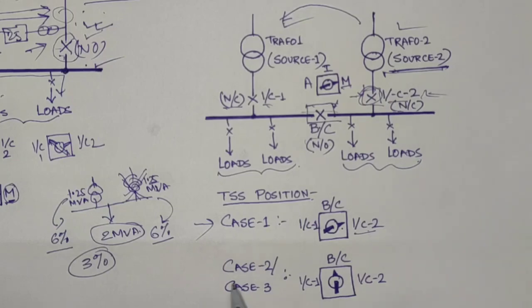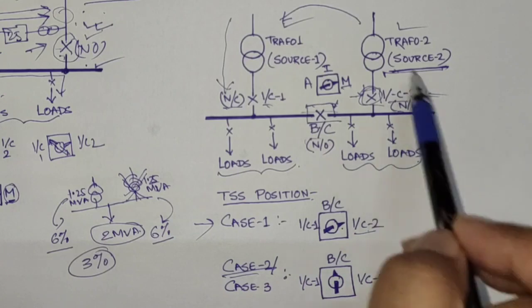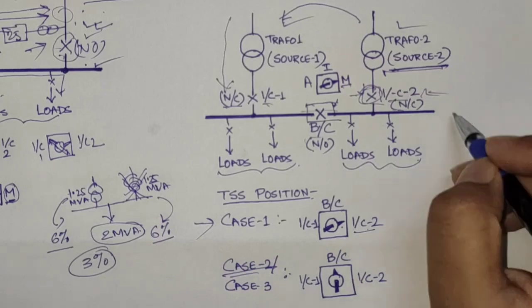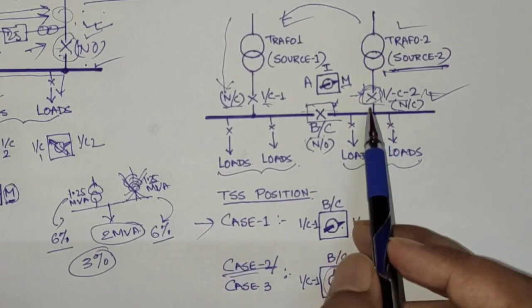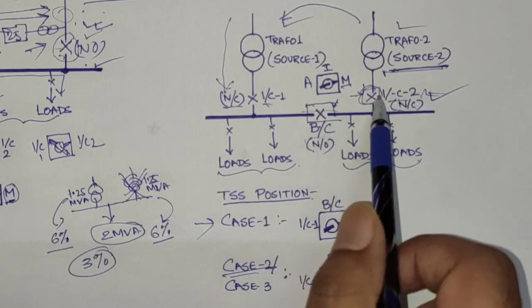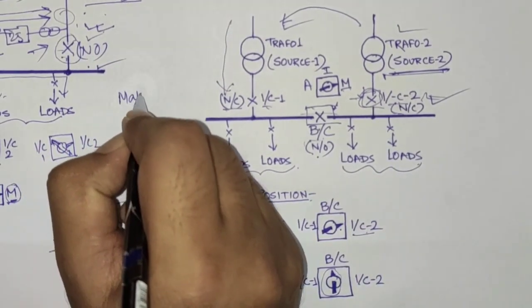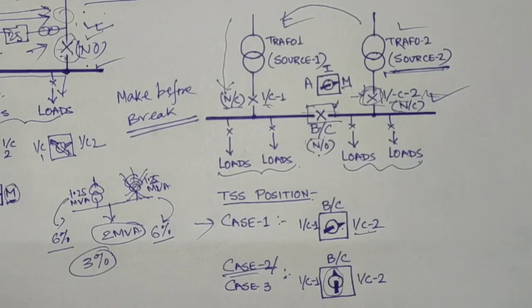In Case 2, Transformer 1 is now carrying the entire bus load after Transformer 2 was taken for maintenance. Now Transformer 2 has been maintained and we want to restore it to the circuit. We close Incomer 2 and trip the bus coupler — so the trip selector switch is set to the bus coupler. We give a closing command to Incomer 2; the synchro-check relay checks the voltage and allows closing, then trips the bus coupler. Remember: momentary paralleling is a make-before-break operation — the closing is done first, then the tripping.